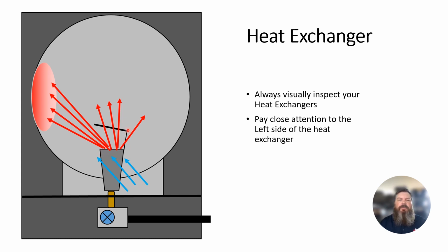Out in front of this burner, you also have a flame spreader. This flame spreader is angled and it favors the left. So naturally, this flame, as it's coming out of the burner, hits the flame spreader and is favoring the left side of this heat exchanger.